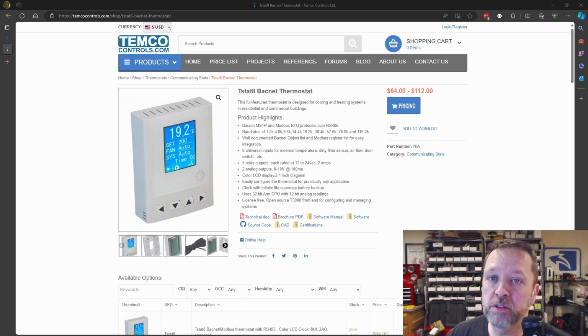The way Modbus works is these devices have what are called registers. Basically, think of it as an array of 2-byte values that you're going to read and write to. Now, Modbus does have coils and inputs and some other things, but for registers, they're generally speaking a bunch of 2-byte values, and those values might be read-only or read-write.